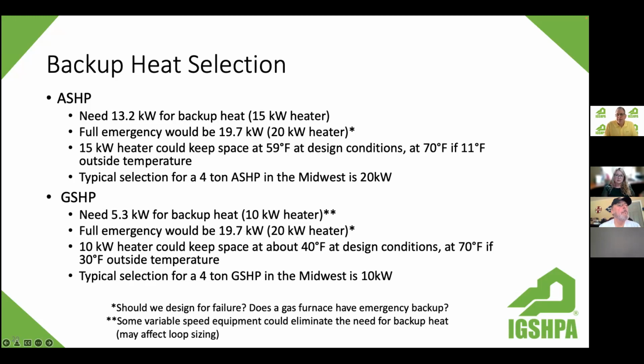And that's a good thing, because if you plan for failure, then you're kind of jinxing yourself. You're hopefully not going to need it. If you have a pump failure or something like that, I suppose the unit could be offline. But even this 10 kW heater is going to keep that space above freezing, so you're not going to have pipes freeze or anything really traumatic if that heat pump's not running. So typically we would see a 10 kW heater on the geothermal application and 15 or 20 on air source.